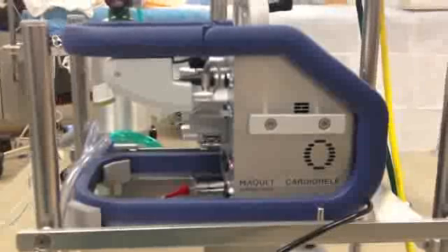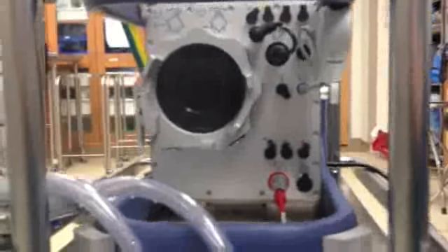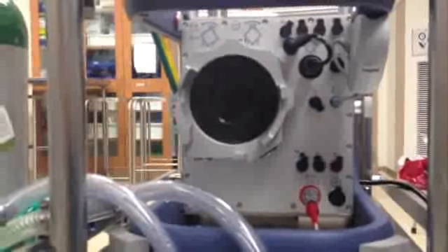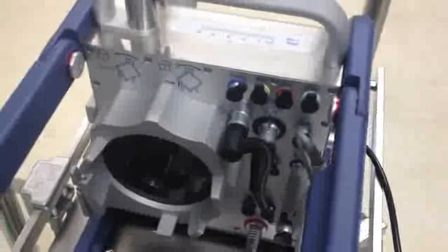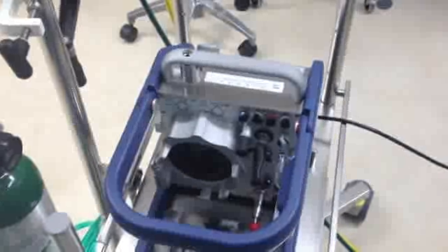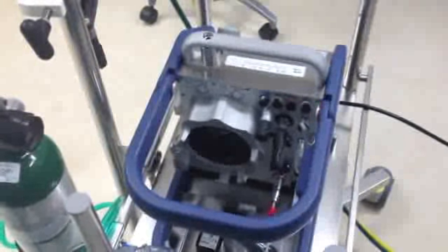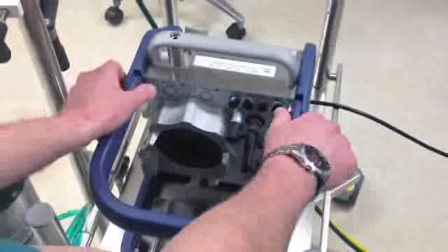Here's the side with the blue guard, and beneath that the venous probe. It's attached. And in the back here you can see the black circle. That's where the HLS set will attach, and to about 1 o'clock there's an integrated sensor connector, which is just resting on its port. And here you can see the 2 red buttons on each side of the guard that are used to unlock the guard, which our perfusionist is about to do. You have to push both buttons in order to raise the guard.